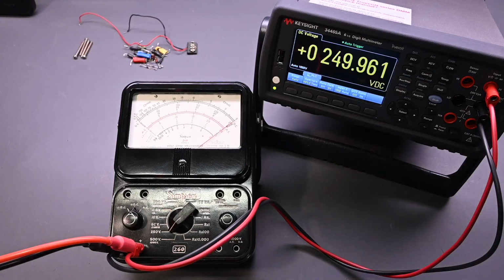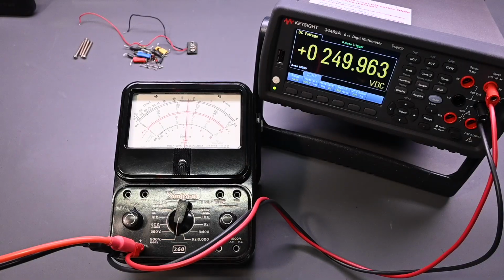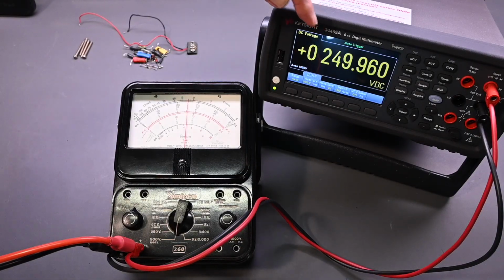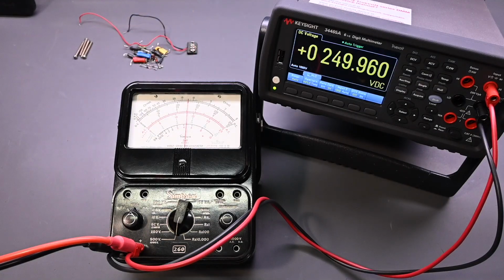All right, so now let's go here and step this up to the next range. So this is 500 volts full scale. That looks great. 250 volts, that's midpoint, and look at that, it's right on. Perfect, no problems there. Let's go all the way up to 500 volts. So getting there, let's see, 400. There's 500, oops, a little bit too far. There, that looks pretty close. Perfect. Right on full scale. So the accuracy of the meter looks excellent. I'm really happy with the results.